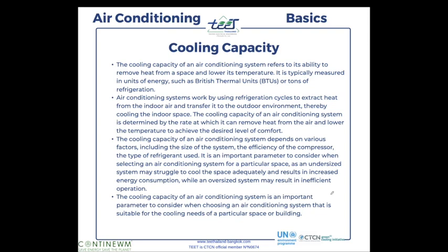Okay, you have 250 square meters, 5 air conditioners of 40,000 BTU, so 40,000 times 5 machines is 200,000 BTU for 250 square meters. Even if we don't say that to the owner, immediately we have that calculation in mind, and we know briefly if the cooling capacity is already good, so it gives us good information on the efficiency of Continewm.